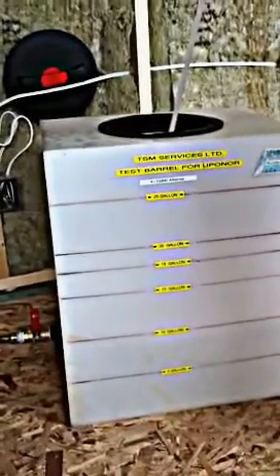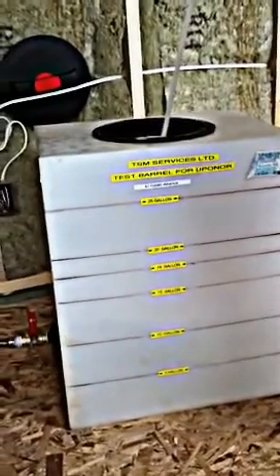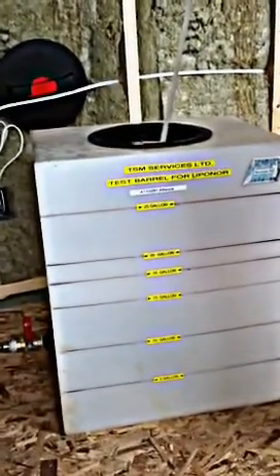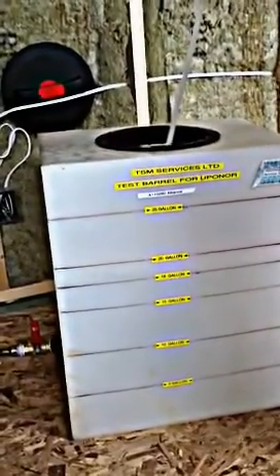You can see on the side of the tank that we have graduated levels. We've already passed five gallons and we're coming up to 10 gallons now. Terry, how many gallons do we need to flow in the first minute? 18 gallons. We're at about 12 gallons now — what's our time? About 30 seconds. Now we're coming up to 15 gallons, and we're getting close to 18 gallons — easily past 18 gallons now.